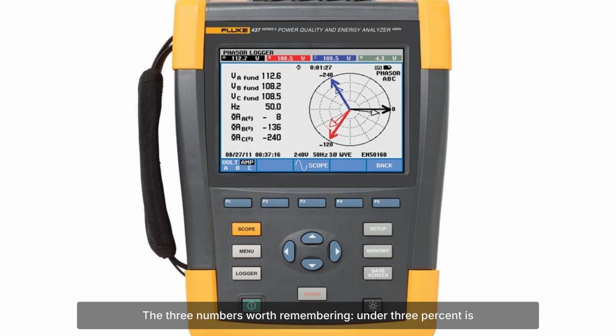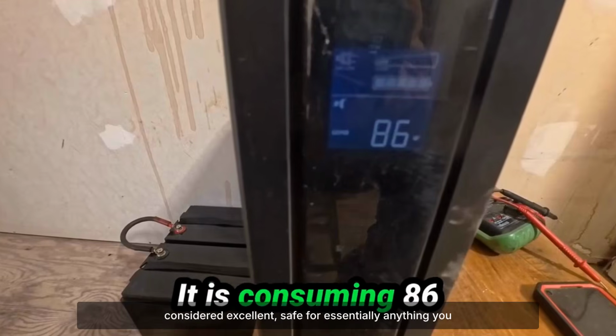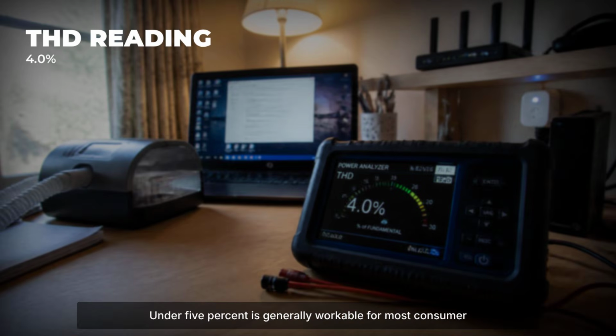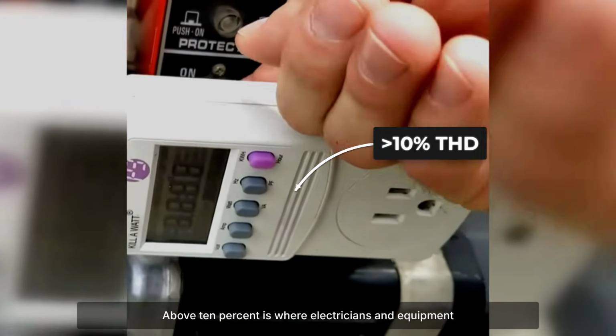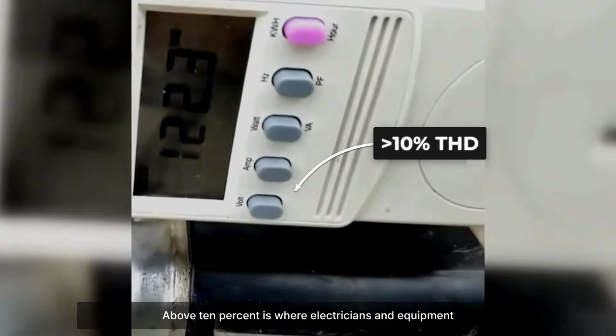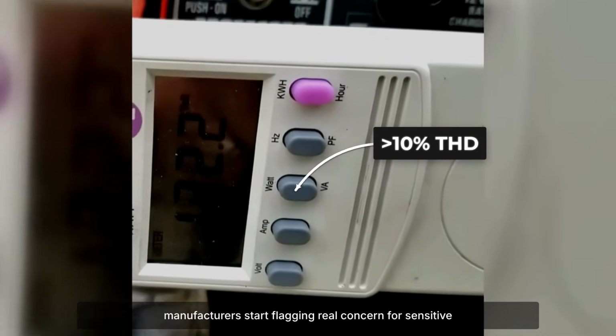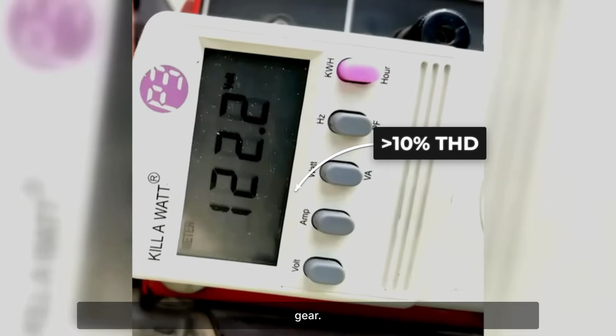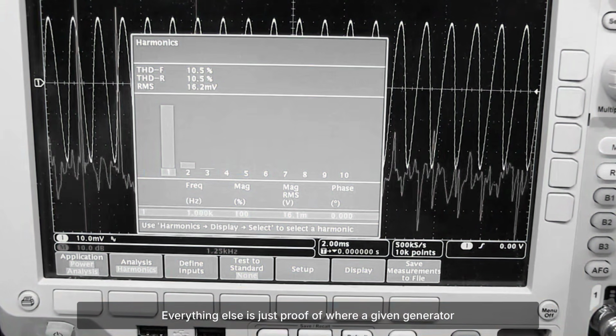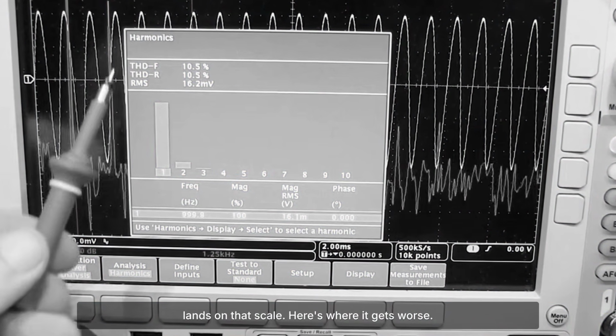The three numbers worth remembering. Under 3% is considered excellent, safe for essentially anything you would plug in. Under 5% is generally workable for most consumer electronics. Above 10% is where electricians and equipment manufacturers start flagging real concern for sensitive gear. Everything else is just proof of where a given generator lands on that scale.